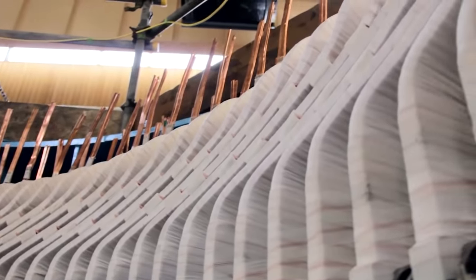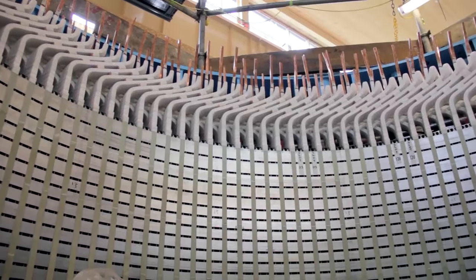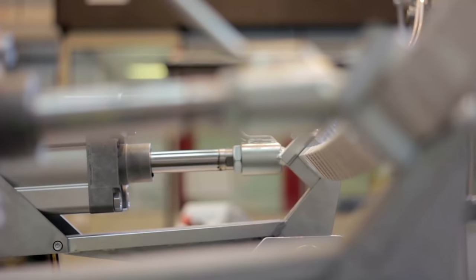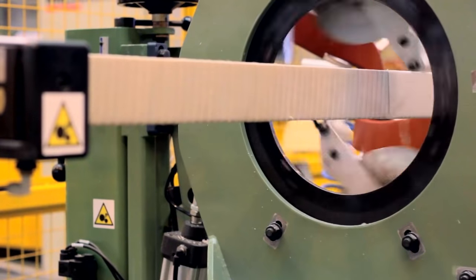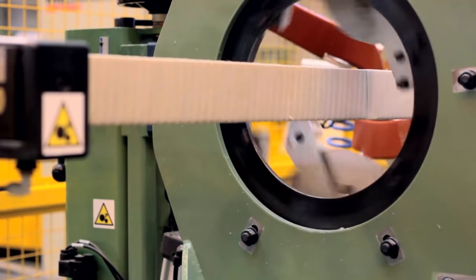There are 126 coils going into the machine — that's what came out and that's what's going back in. There's more copper within them now, so the actual connections of those coils are different. Forty years of coil innovation has brought much more repeatable processes. The coils are manufactured and pulled out on machines that give the same dimensions for each coil, so there's less need for mechanical manipulation during winding. The tapes are applied by machine, giving even tension and an even number of layers.